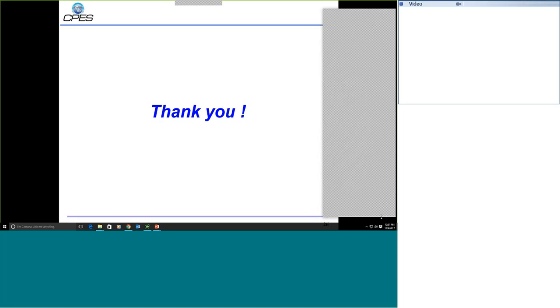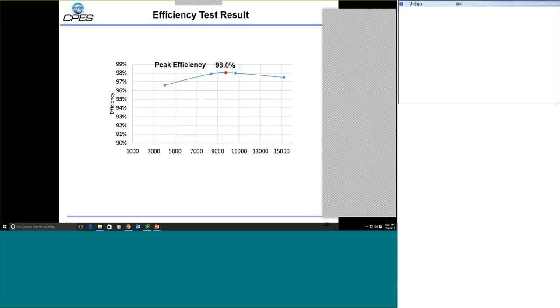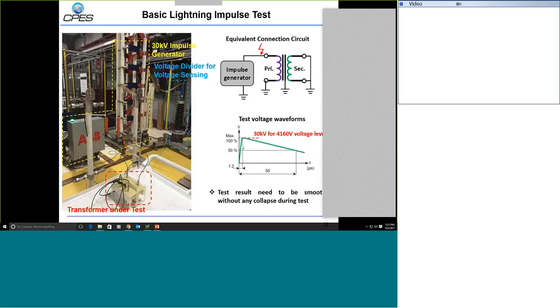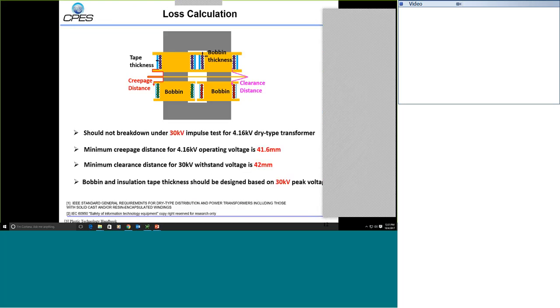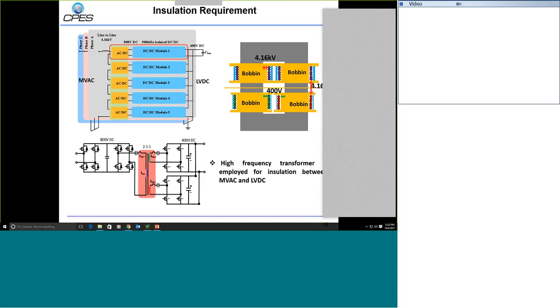A second question asks about the switching frequency range when regulating the load. Right now we fixed the switching frequency at 500 kHz, because for this structure we can use the AC-DC stage to adjust the input voltage of the DC-DC stage. We design the DC-DC module like a DC transformer for the first step, and if the output voltage changes, we rely on adjusting the 800-volt input to accommodate the output voltage change. So yes, we will adjust the AC-DC output voltage.